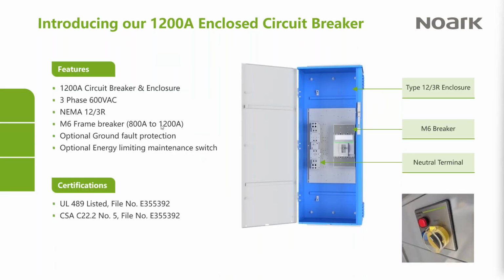Rob, if you don't mind, we just got a few great questions. Will all 800 amp and 1200 amp have a flange handle with aircraft cable operating? Yes. Okay, I like that. Can you purchase the empty enclosure by itself, and does the CSA and UL certification cover the electrician adding a loose breaker and neutral kit in the field? Yes, on our standard enclosures up to 600 amps today, they are listed by UL and for CSA to be field assembled. So they're perfectly fine to be assembled by the customer.